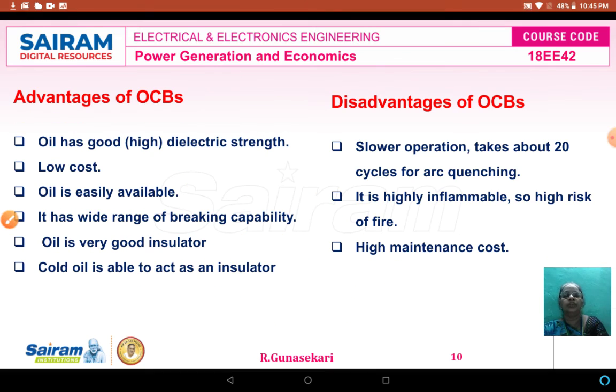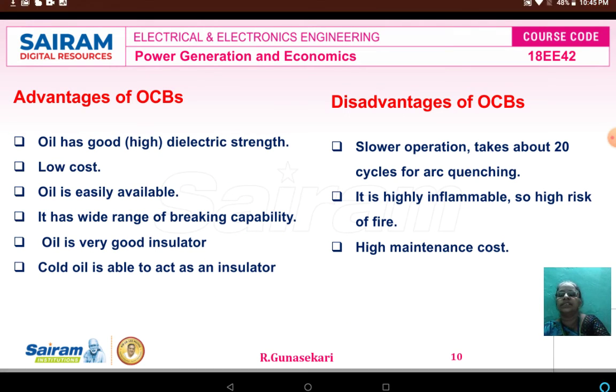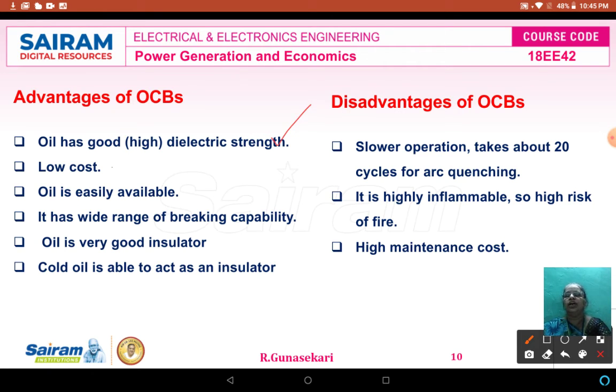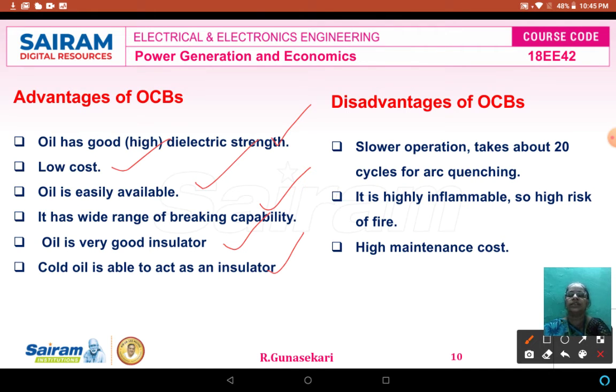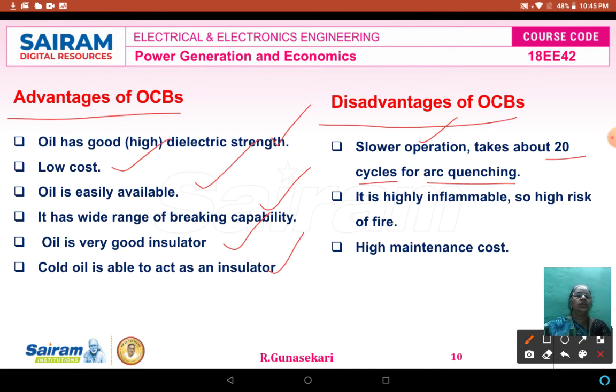Advantages of oil circuit breaker: the oil has good (high) dielectric strength, low cost, oil is easily available, it has wide range use due to high breaking capacity, and oil is a very good insulator. Disadvantages of oil circuit breaker: slower operation — 20 cycles for arc extinction — it is highly inflammable so there is high risk of fire, and high maintenance cost.